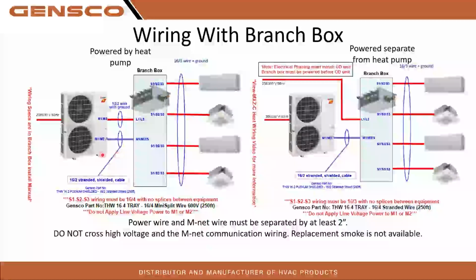Now, your communication between your heat pump and your branch box, your M1, M2, otherwise known as MNet. This one is a very specific wire. If there's any one wire you're not going to screw up and you're going to make sure is the right one, no matter what, it is going to be this M1, M2. And that should be a 16/2 stranded shielded wire. This is the wire that has all the communication happening from your branch box, or all of your indoor equipment, to your heat pump.